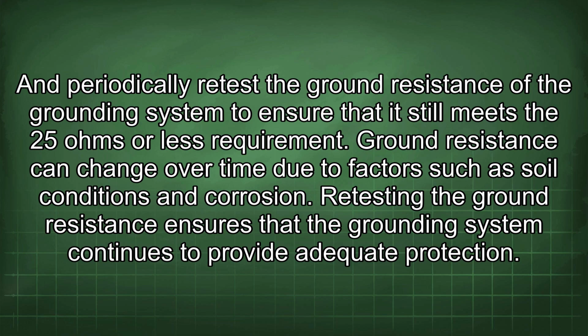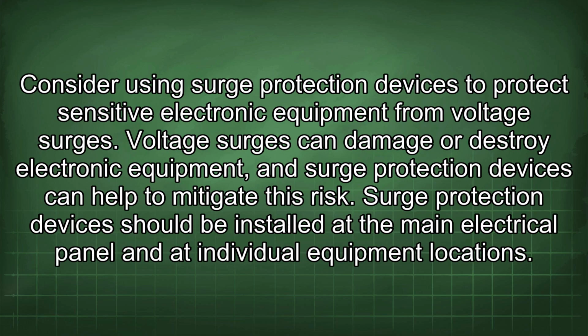And periodically retest the ground resistance of the grounding system to ensure that it still meets the 25 ohms or less requirement. Ground resistance can change over time due to factors such as soil conditions and corrosion. Retesting the ground resistance ensures that the grounding system continues to provide adequate protection. Consider using surge protection devices to protect sensitive electronic equipment from voltage surges. Voltage surges can damage or destroy electronic equipment, and surge protection devices can help to mitigate this risk. Surge protection devices should be installed at the main electrical panel and at individual equipment locations.